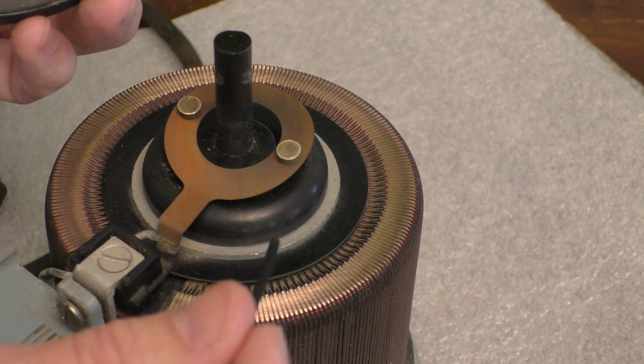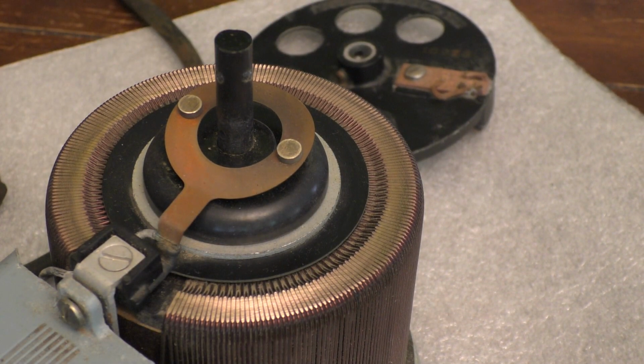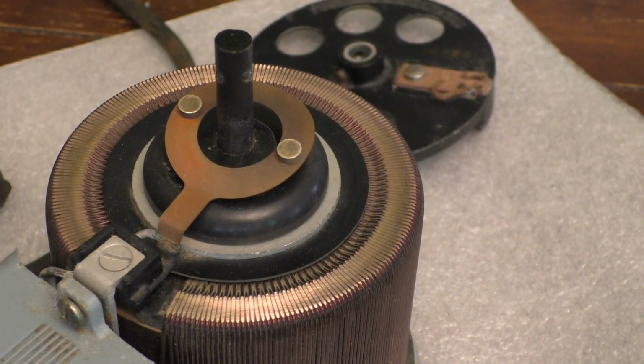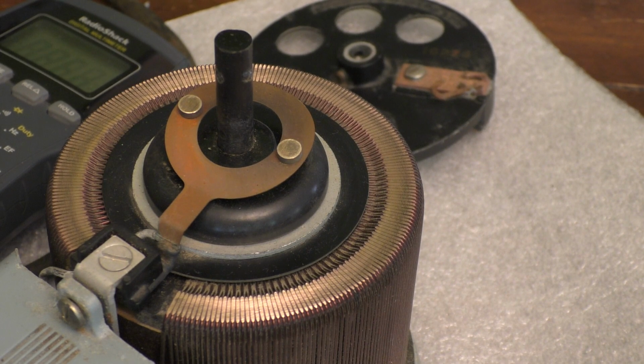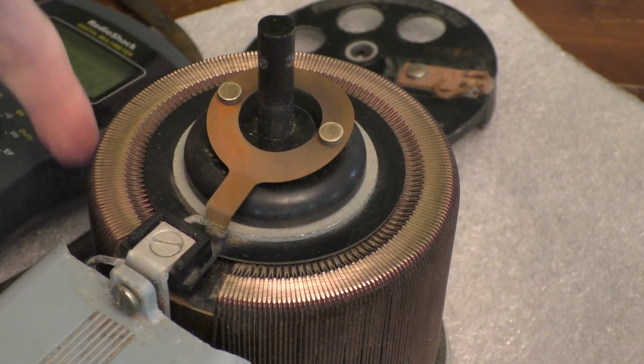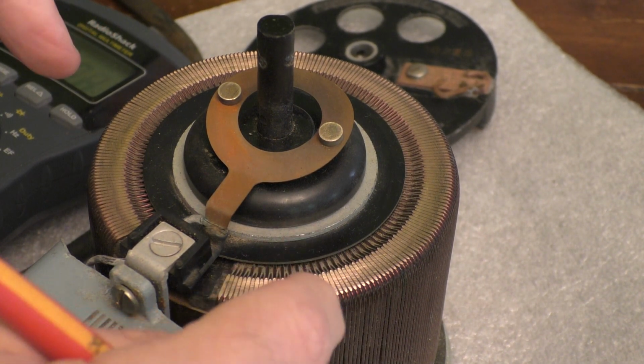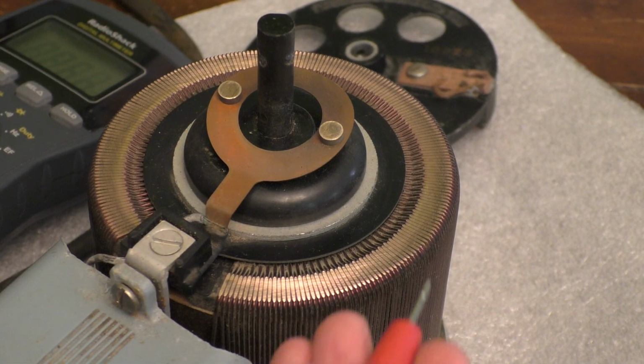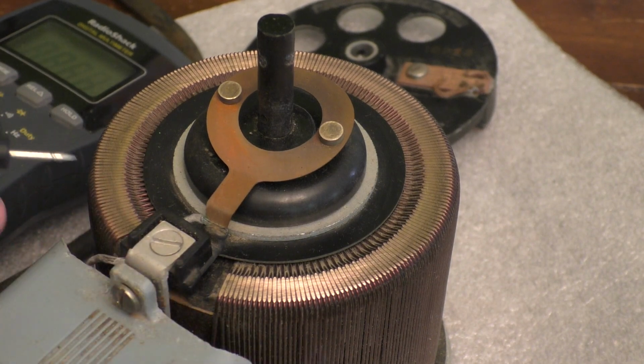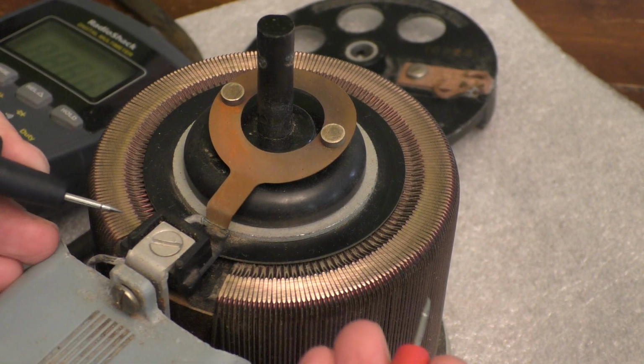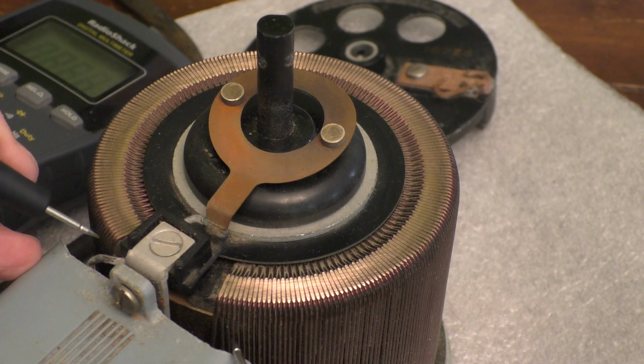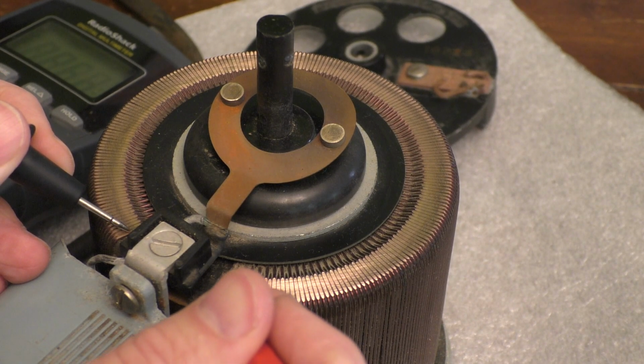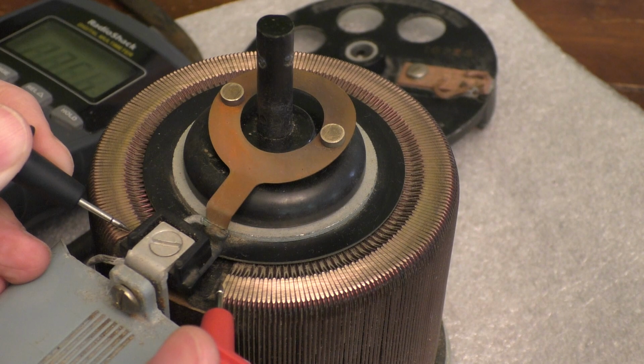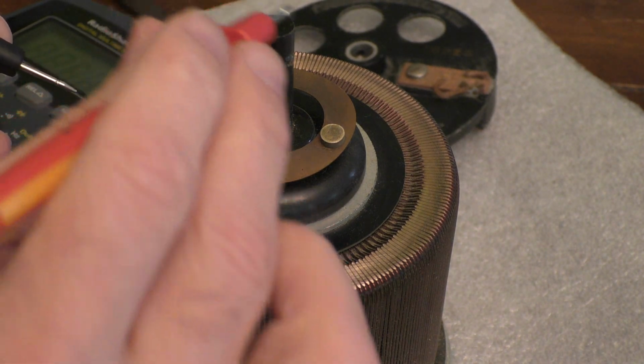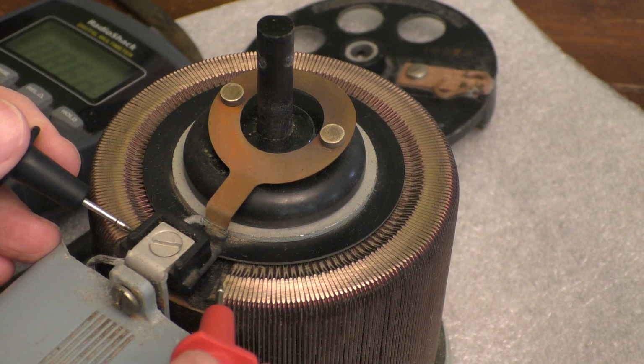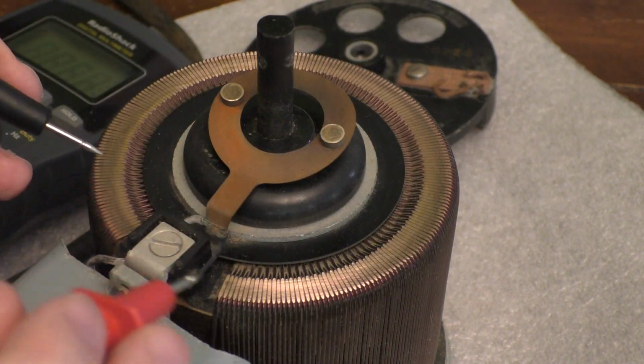Now, one thing to test the coil: take your multimeter and put it into continuity mode. Sometimes these coils burn out, and if they do, they usually lose continuity. So one way of checking that the coil is good and the machine can actually work is to put it on continuity, go to the start of the coil and the end, touching the exposed portions, not these insulated ones. If those are in continuity, you know the wires are fully connected all the way around and haven't burnt out. So as long as you have continuity between the first and end points, your coil winding should be good.